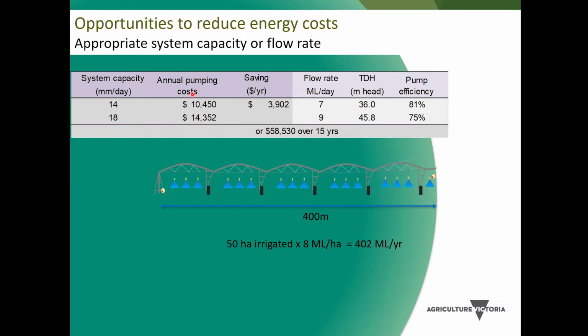And here we've got the annual cost of those two systems. So it's exactly the same system, just pushing different amounts of water through it. It's costing us an extra $4,000 to have that 18 mil system capacity, and that provides no benefit whatsoever. So over a 15-year period, that's costing almost an extra $60,000 in pumping costs. And that's all just because we're trying to push this extra water through the pivot, increasing total dynamic head. And in this case, it's also reducing the efficiency of the pump.